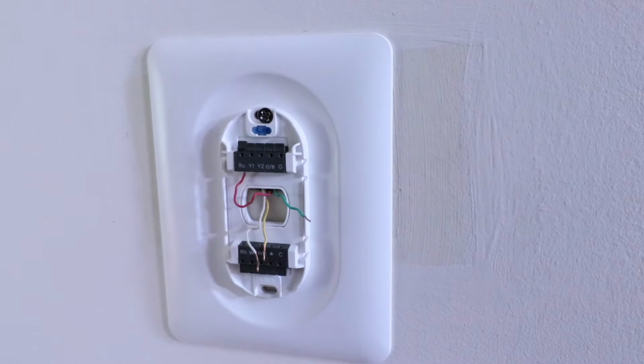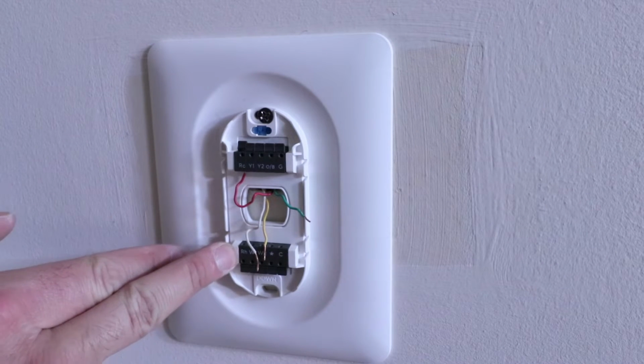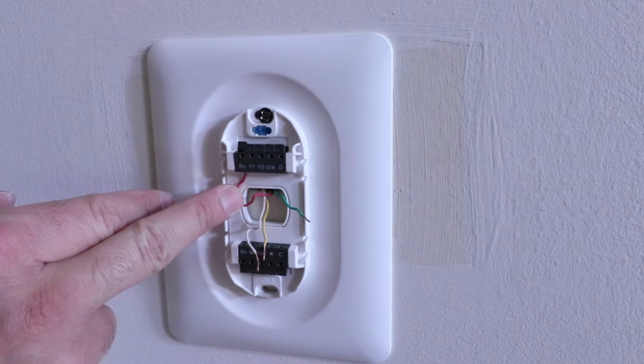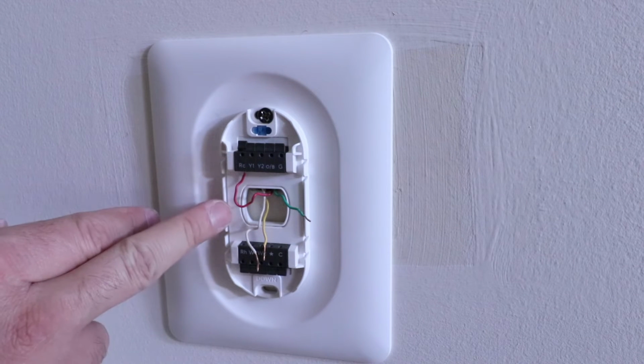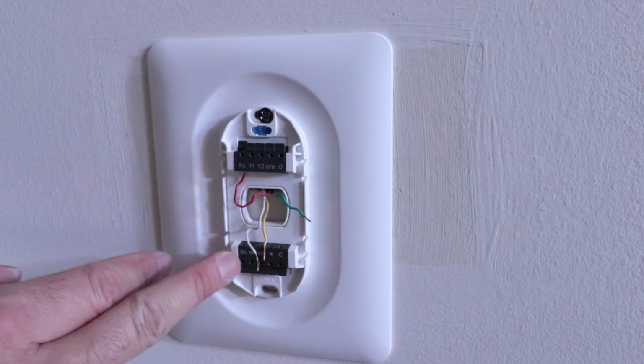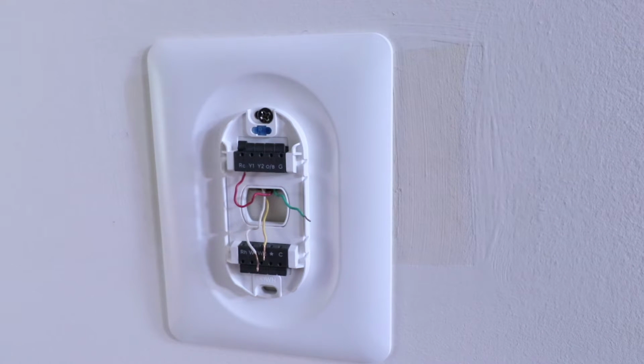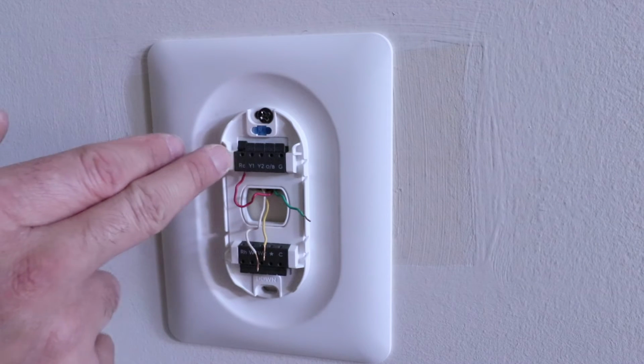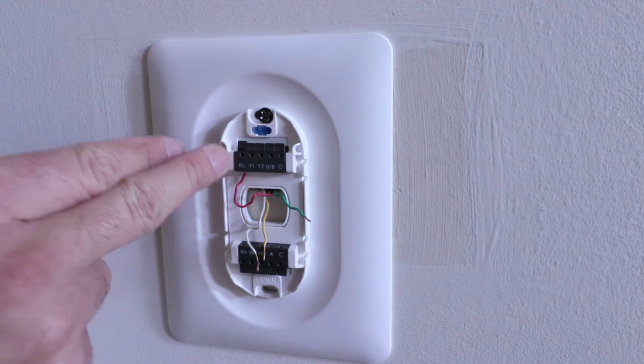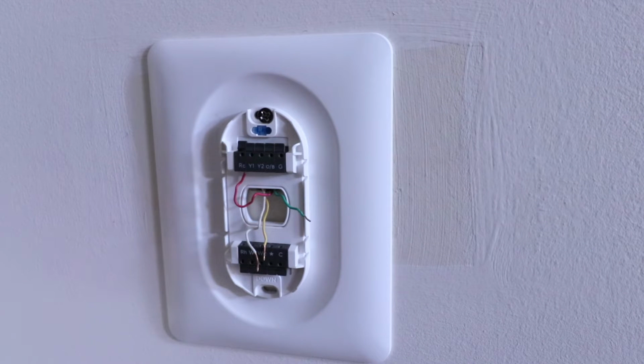We do not have that, and most people won't have that condition. But if you had both an RC wire and an RH wire, you'd want to connect the wire that was on RC to the RC terminal, and the wire that was on RH to the RH terminal. If you have just one red wire connected to an RC, RH, or R terminal, they all mean the same thing, power, in a system that only has one power source. So you want to connect it to the RC terminal here at the top, because this is the main power terminal when you don't have a dual fuel system.